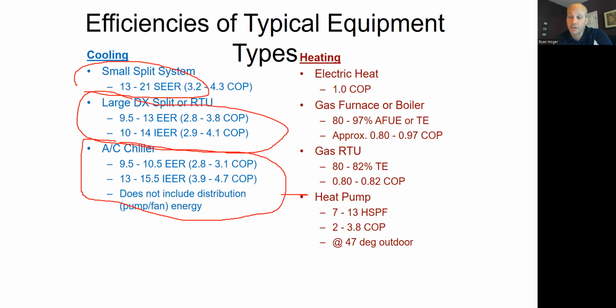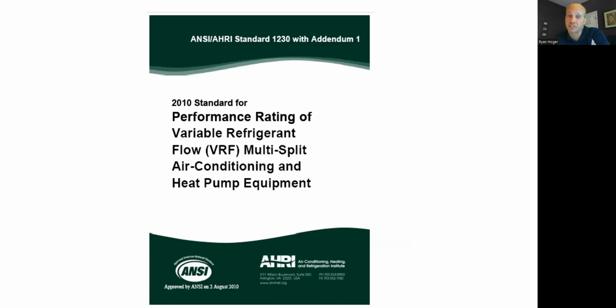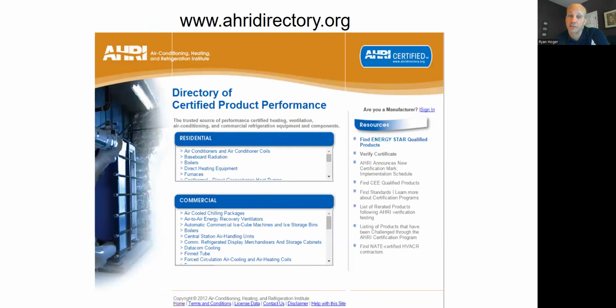So we can get ratings for VRF. The ratings from AHRI are very good for comparing manufacturer A to manufacturer B of VRF. They are not good for comparing manufacturer A of VRF to manufacturer C of chiller. Doesn't do a good job of that. You have to energy model for that kind of thing. We've had this rating system for 13 years now for VRF. Before that, it was the Wild West, and everybody just claimed whatever they wanted to claim. Now we have a rating system. It's treated like all the other products.